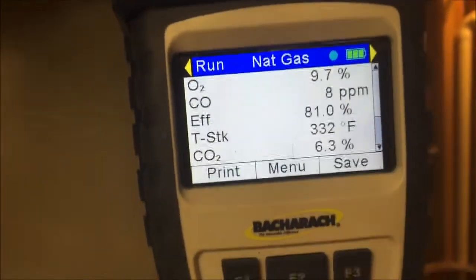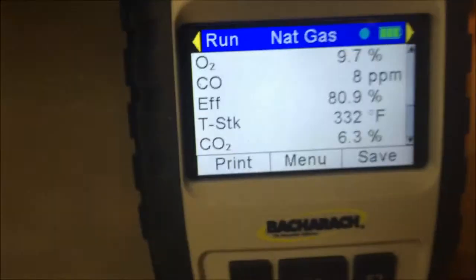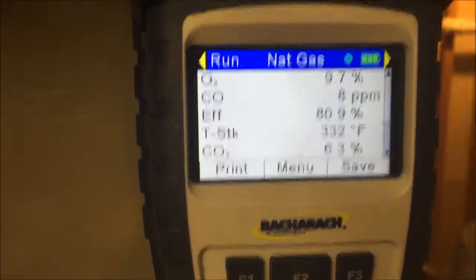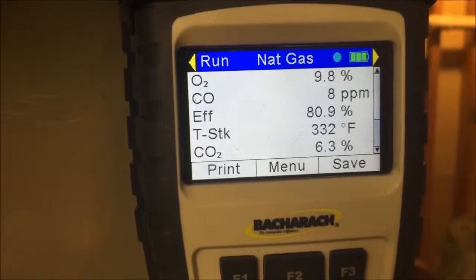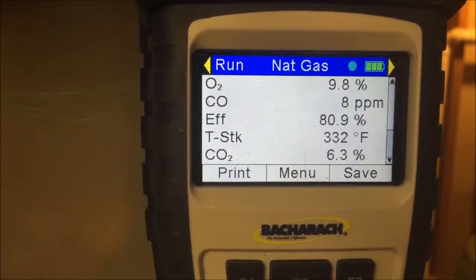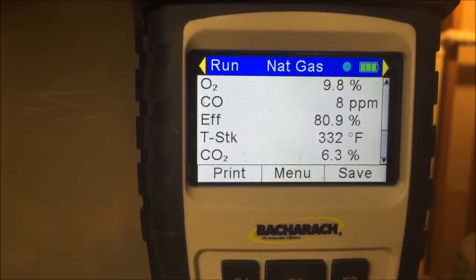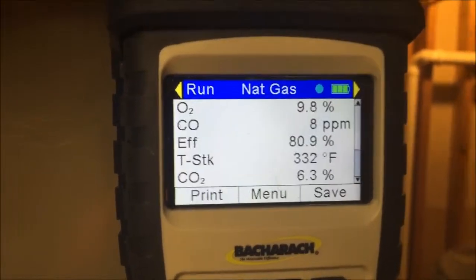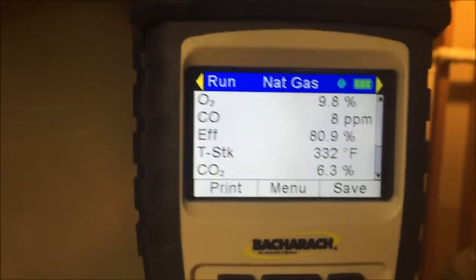I pulled the probe out. I pulled back on it a little bit to cheat it, just enough to where it's still got temperature and everything else. So you notice my O2 and my CO2 are off just a little bit. So what I'm going to do is press enter to get my analyzation.